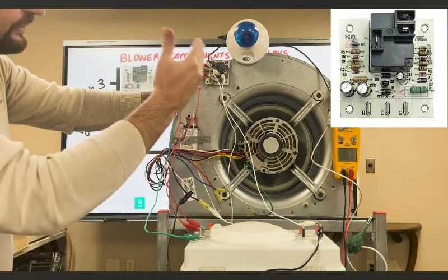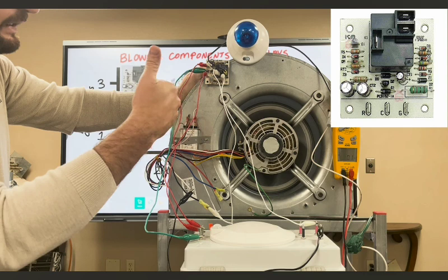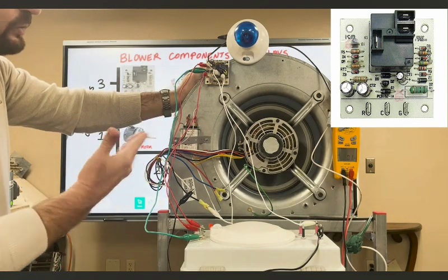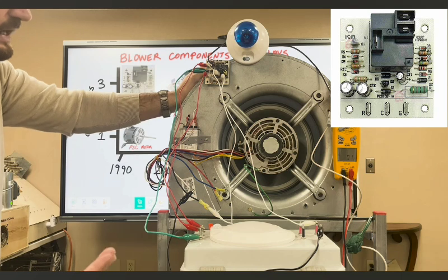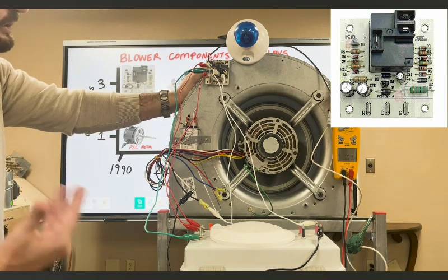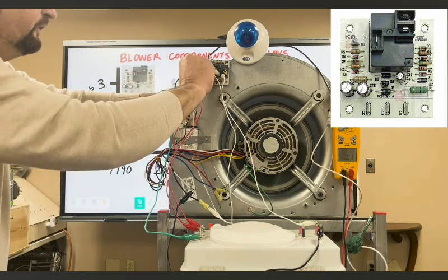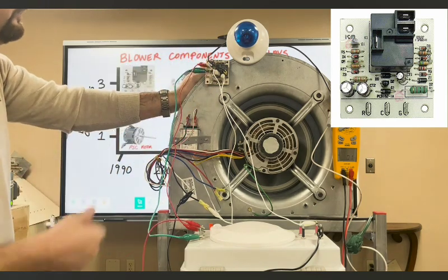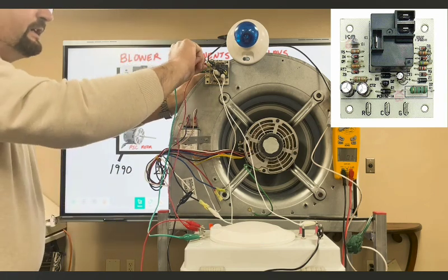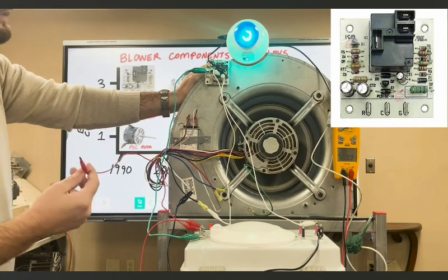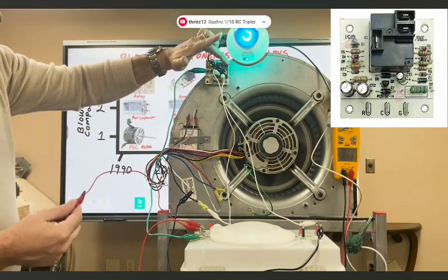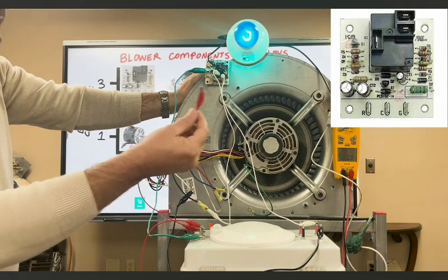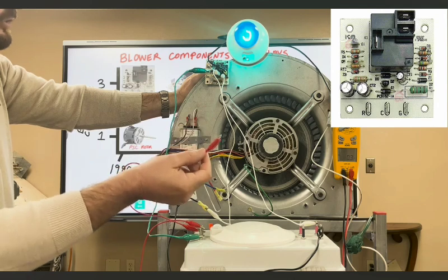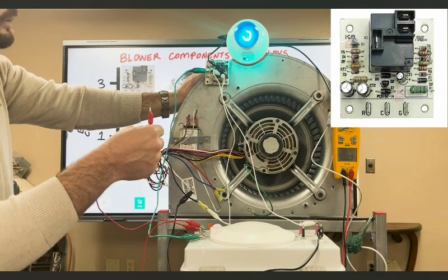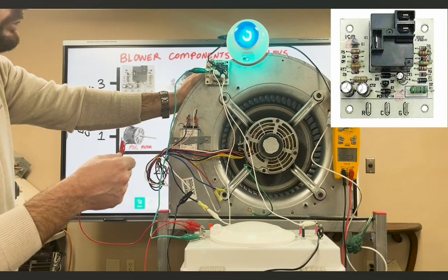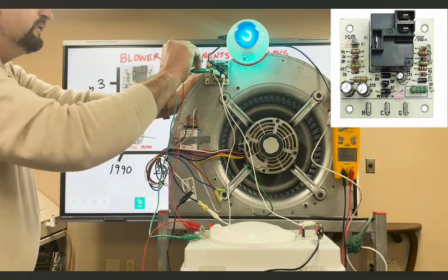I could pick any one of these speeds, whether it's high speed, medium speed, or low speed, and wire it up to it. Your float switch is always wired up to this too, so if you needed everything to shut down, that's pretty much going to happen the moment you lose 24 volts. So let's just say that we weren't getting a G call and say your float switch opened. The moment I lose 24 volts here, the motor shuts off. Now the reason why the light came on is because it's on the normally closed terminal. And so this would represent, hey, we lost power because maybe the fuse is blown, transformer issue, or the float switch was possibly tripped. We're going to go ahead and do that one more time.